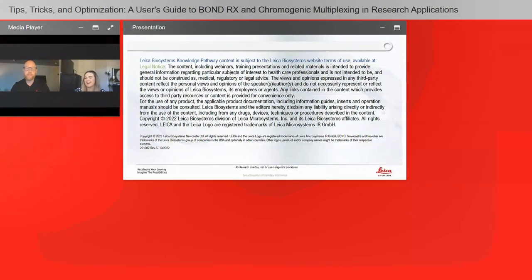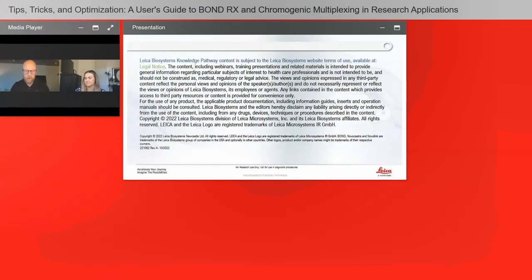Another question: how many chromogenic biomarkers can be stained on one slide using the Bond RX? You can do up to six different biomarkers with six different chromogens. Leica Biosystems has four chromogens: DAB, red, green, and blue. But you can also bring on outside chromogens that are horseradish peroxidase-based.